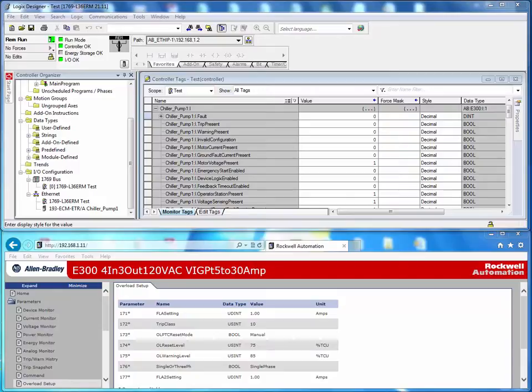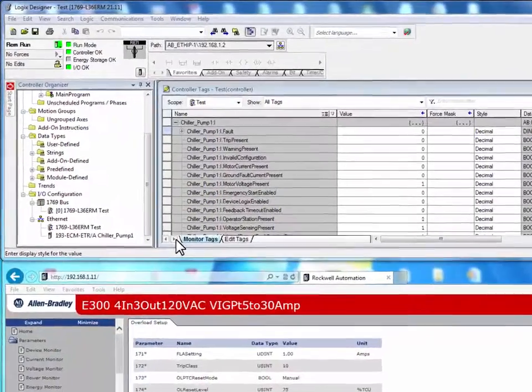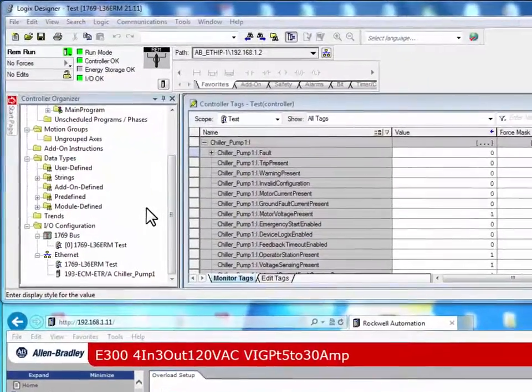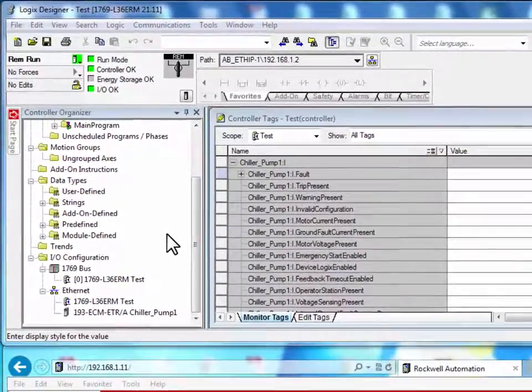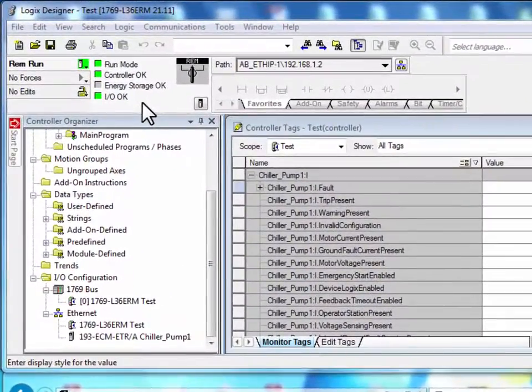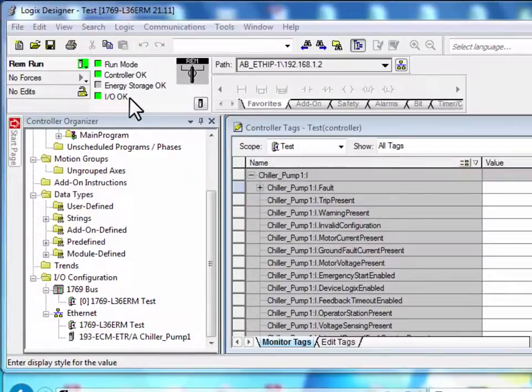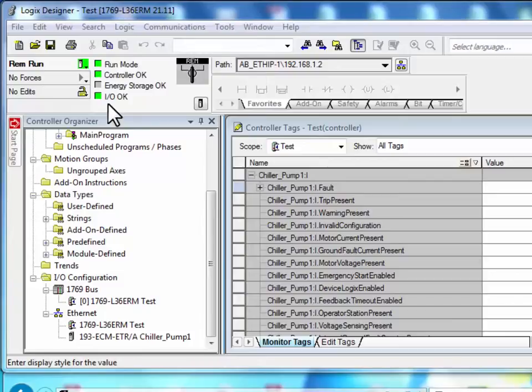This video will show a little example of how automatic device configuration works. The CompactLogix L36ERM is currently scanning the E300 electronic overload relay. You can tell this by the I.O. status light as a solid green.